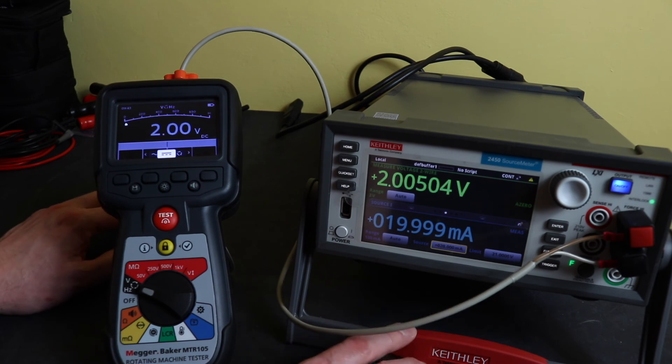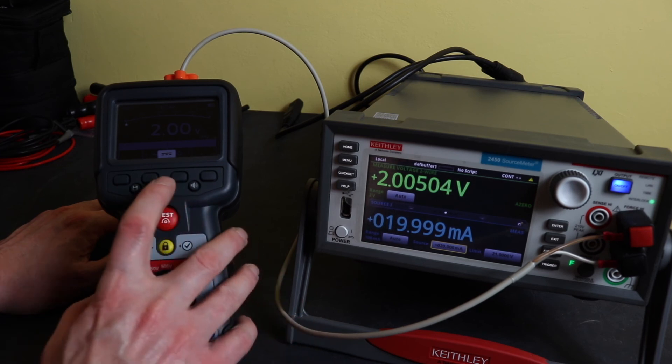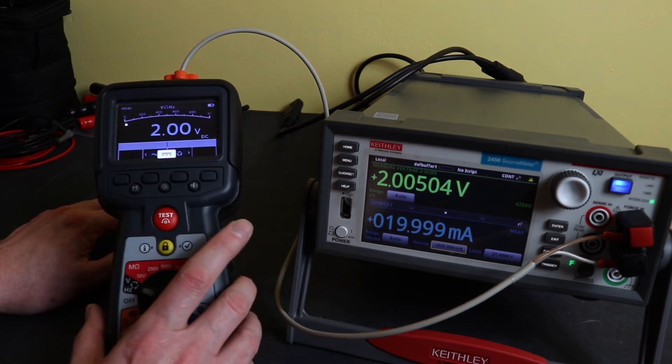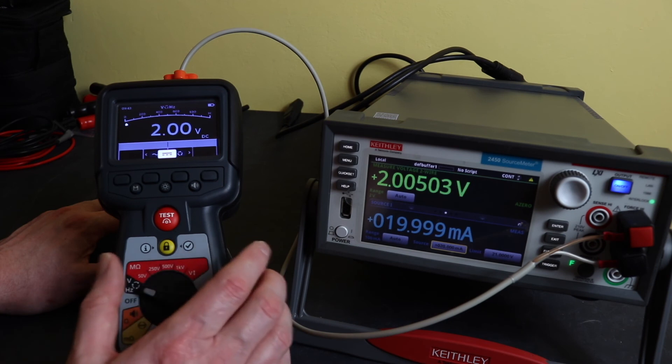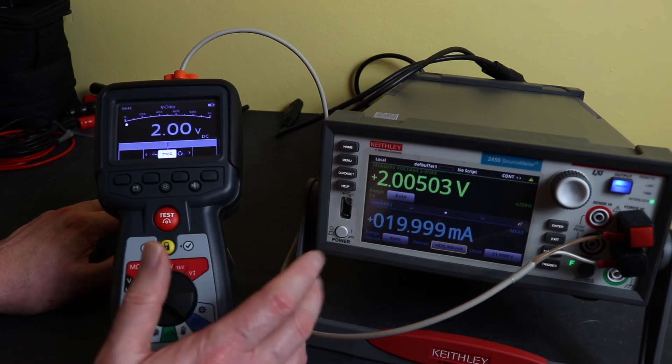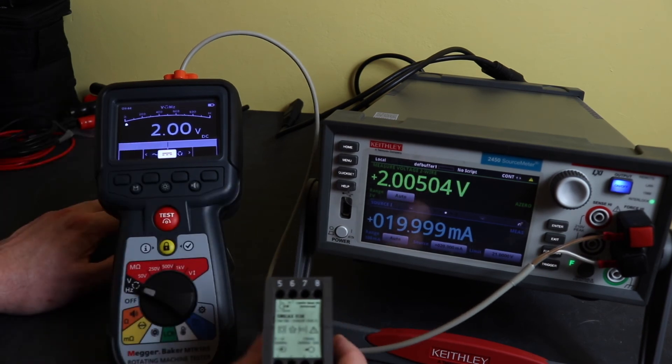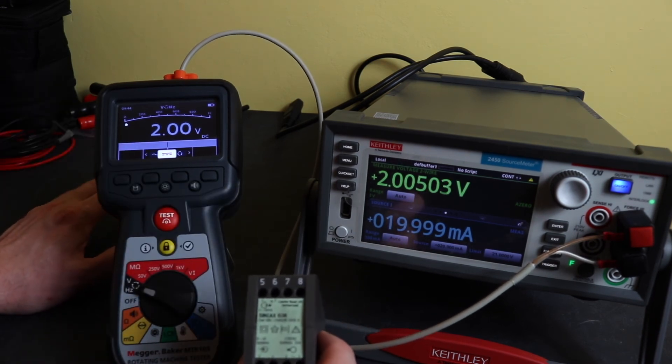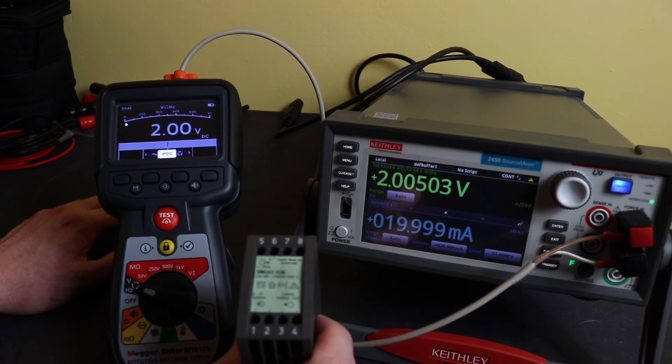Again dividing by 100, but you see the burden is actually 2.005 volts so a little bit more burden would be put onto the actual transducer output. Usually when testing it straight on its own that won't be an issue however if you tested this by putting this in series with the control system you would need to know how much burden the control system, in other words how much voltage the transducer would need to drive in order to get the 20 milliamps through this instrument and the control system as well because these transducers have a limit to them.